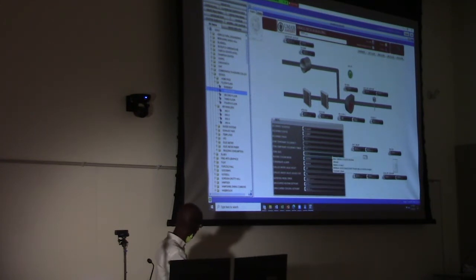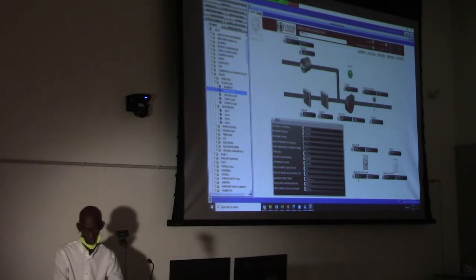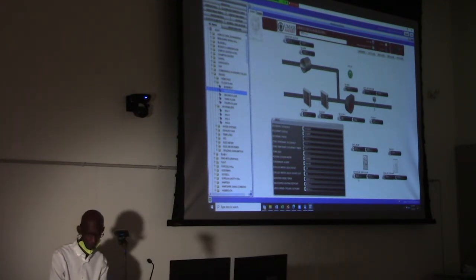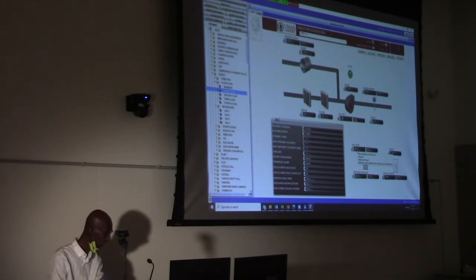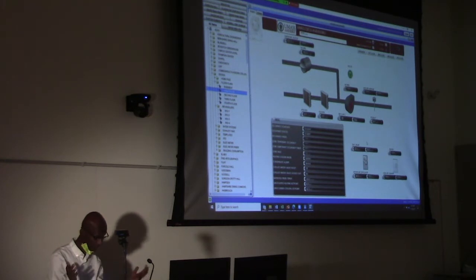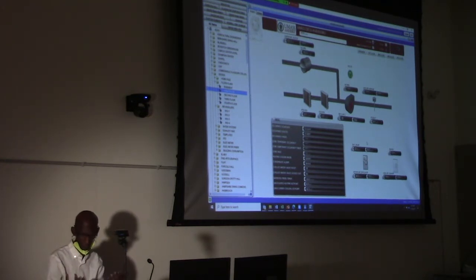Okay, so can you follow my cursor here? The zone temperature is 68.9, and the thermostat is set to 68, which means it's satisfied. It doesn't need heating or cooling, so the fan coil unit doesn't kick in. We don't need heating, we don't need cooling, so the unit is satisfied.